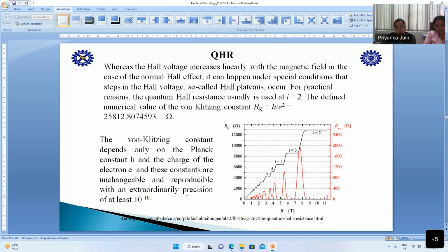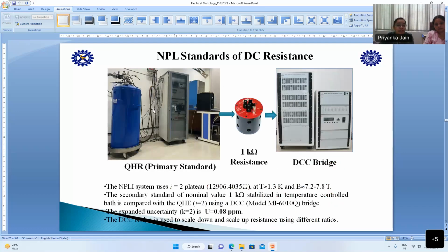power minus 10. So we are calibrating our 1 kilo ohm standard against this QHR. Based on this plateau, this value is generated, and we are comparing our 1 kilo ohm resistance standard against this QHR. Here, this is NPL's QHR standard. Similarly, this is a helium container at 4.2 Kelvin, and we have kept our Hall resistance standard inside it to avoid noise due to temperature.